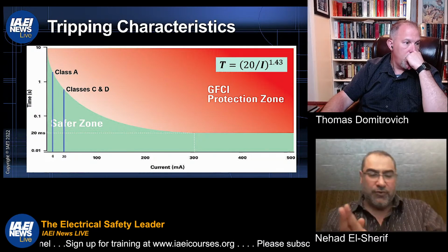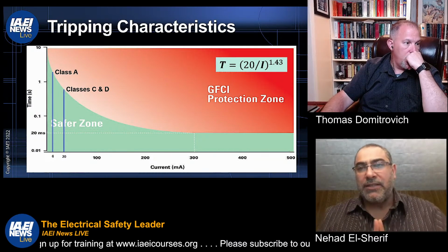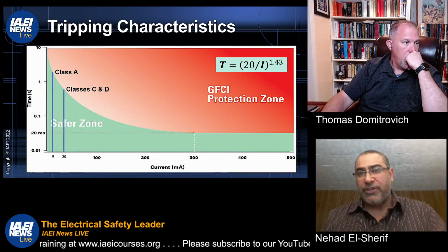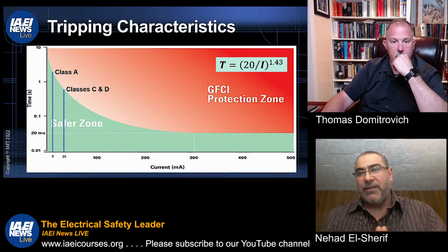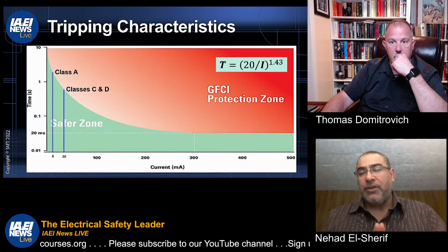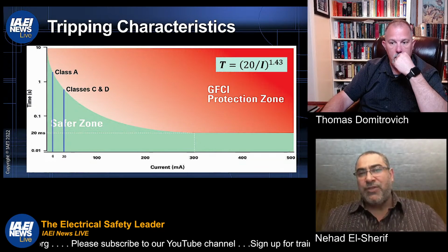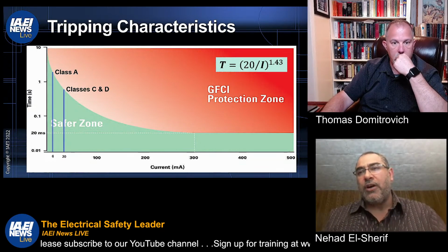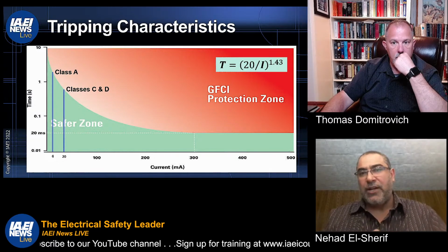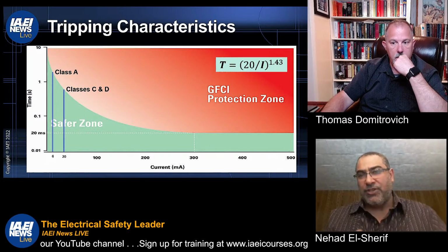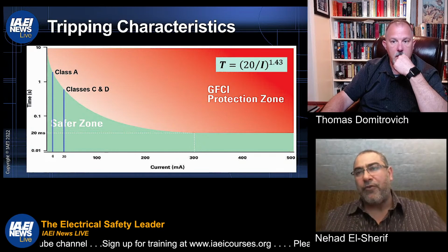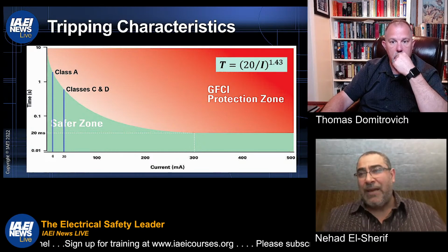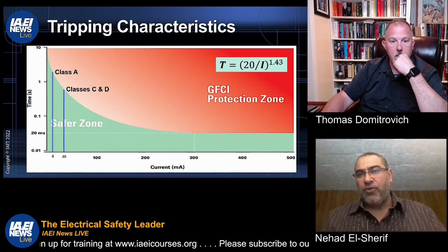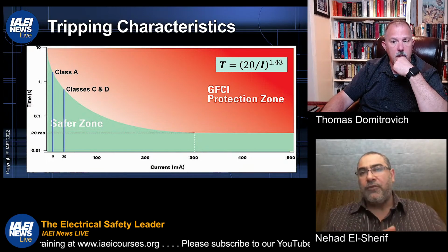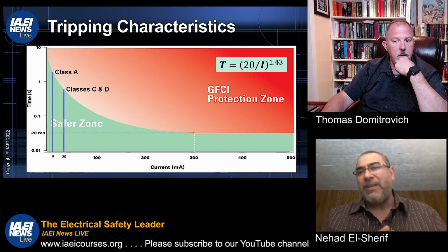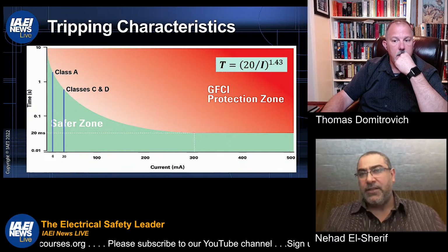Back to the slide, I guess we're running out of time. This slide is to answer Don Guinier's question. Yes, Class A, C, and D use the same equation. Effectively, what we did is we moved the starting point of the tripping curve. Instead of starting this equation, 20 divided by I to the power of 1.43, at 6 milliamp for Class A, you move it to the right a little bit. So now we start for Class C and D at 20 milliamp instead of 6.